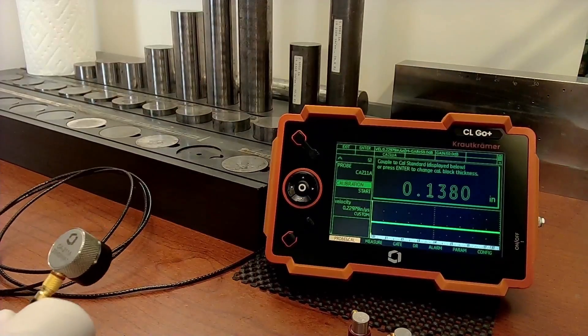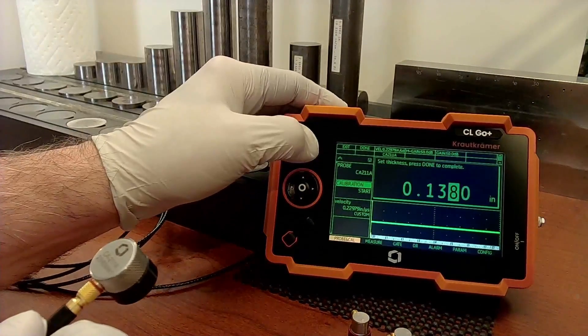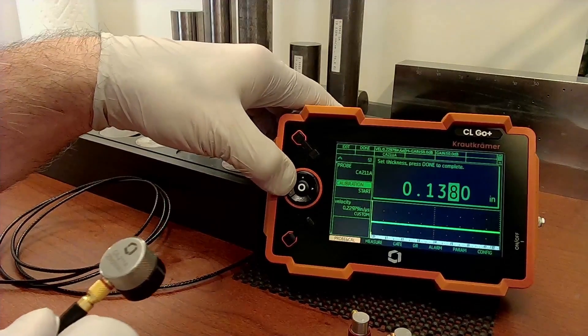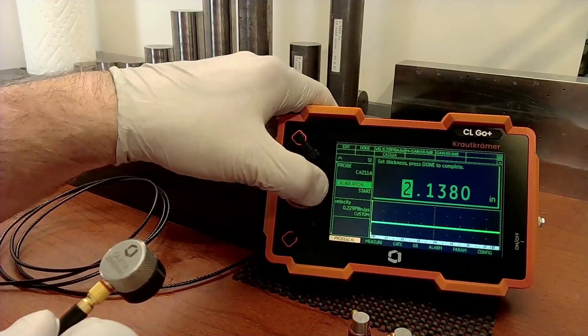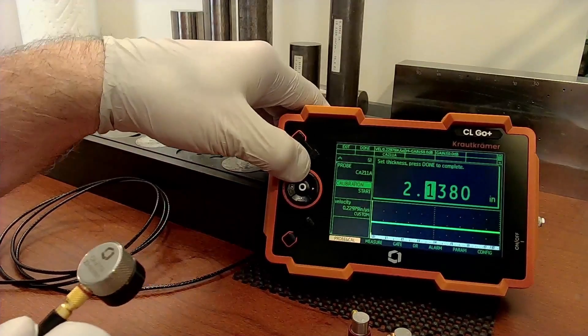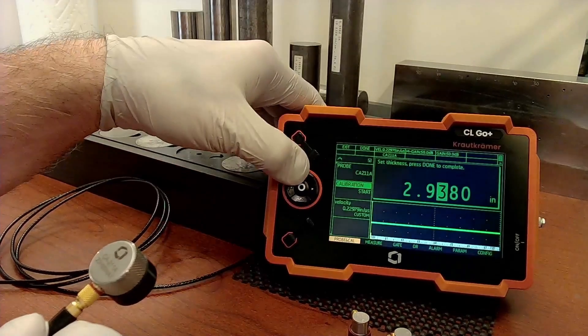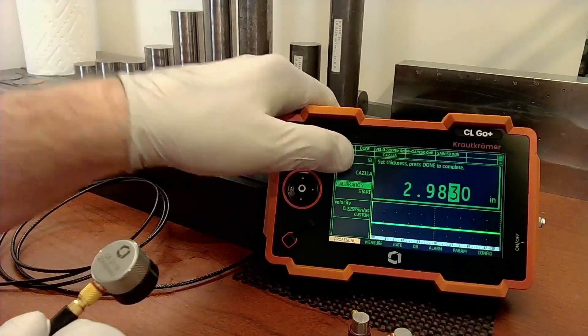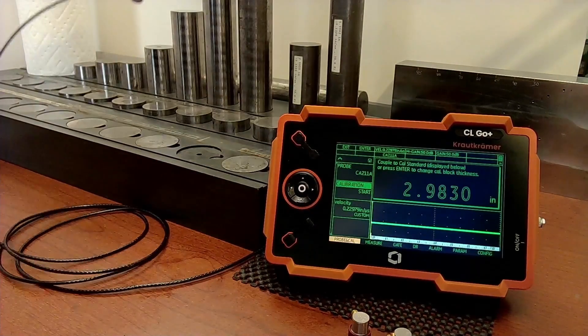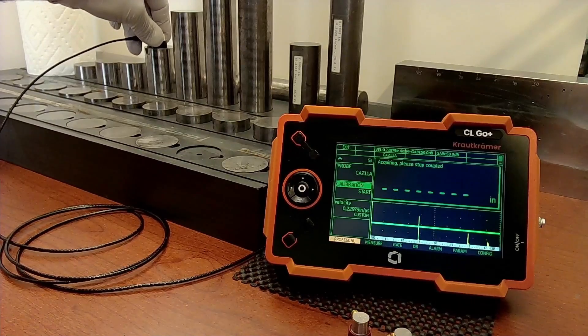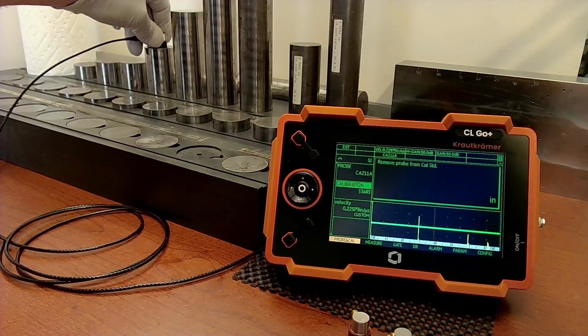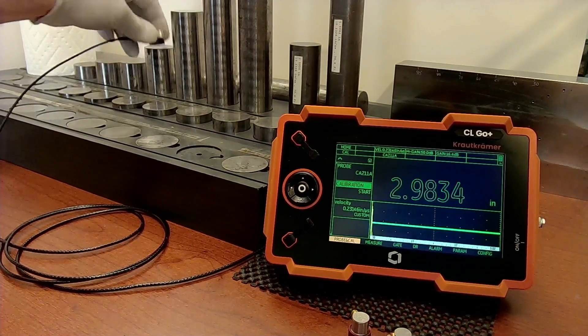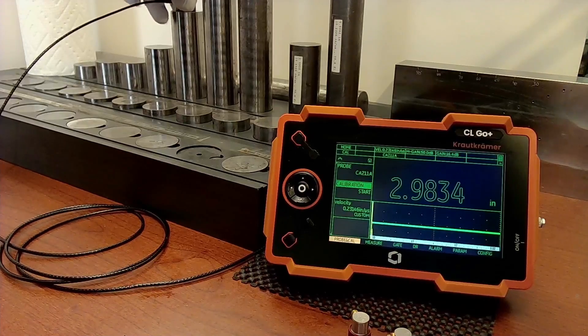And now it's time to go to our calibration block. I'm going to change to a block that's just about three inches. So we're going to say two inches point nine eight three. Okay, we're done. And we'll go to our taller block at two point nine eight three. Instrument locks in. Take it off. Two point nine eight three. And now we can measure our longer blocks.